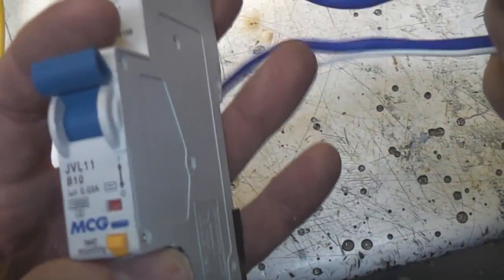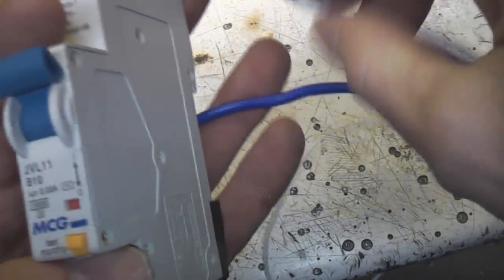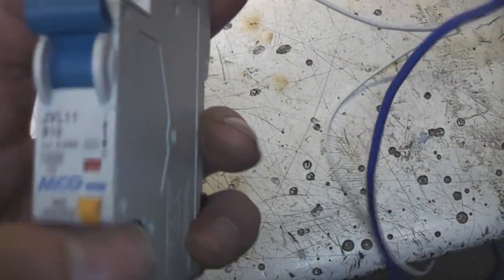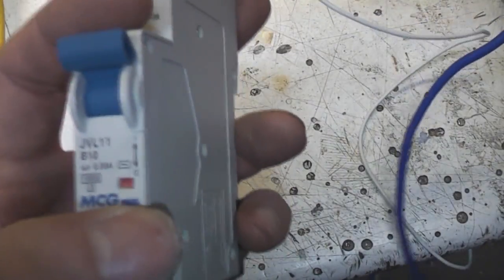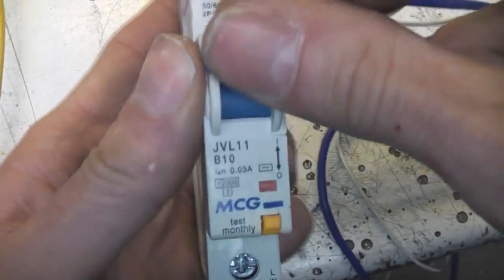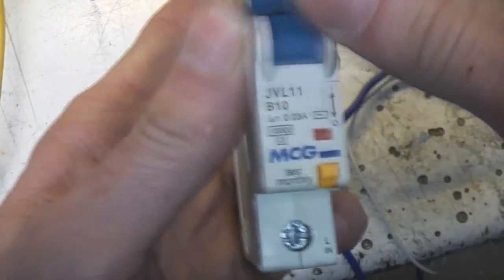It's not going to set the cable on fire because it's a heating effect. So if this conducts 4 or 5 times its nominal current for a few hundred milliseconds, that isn't going to be a problem because it's not going to set fire to anything. So for that sort of load, you use a C or a D breaker.